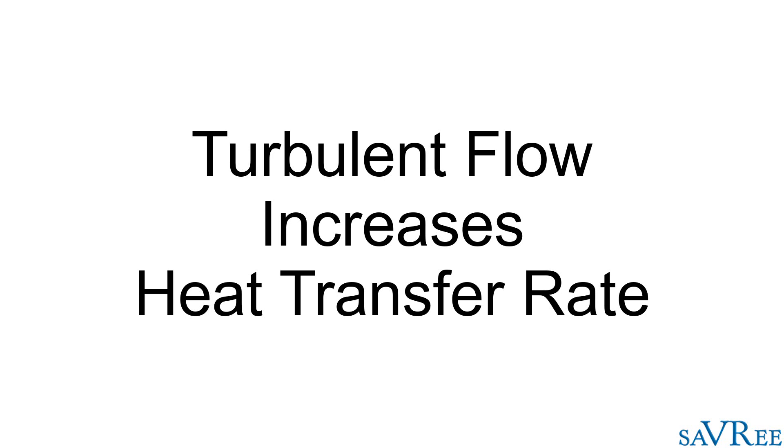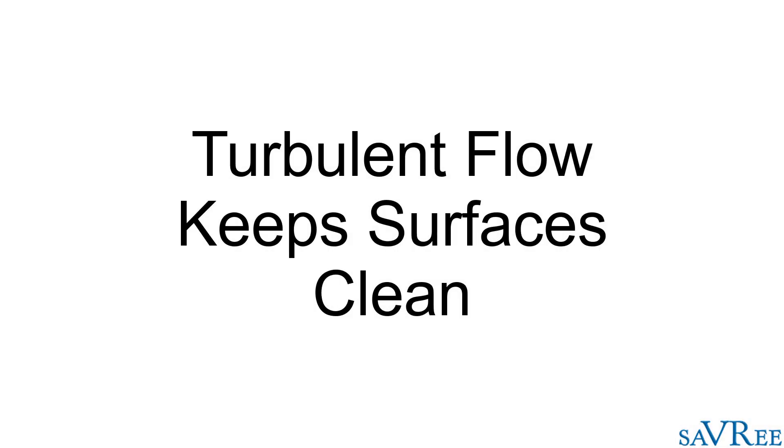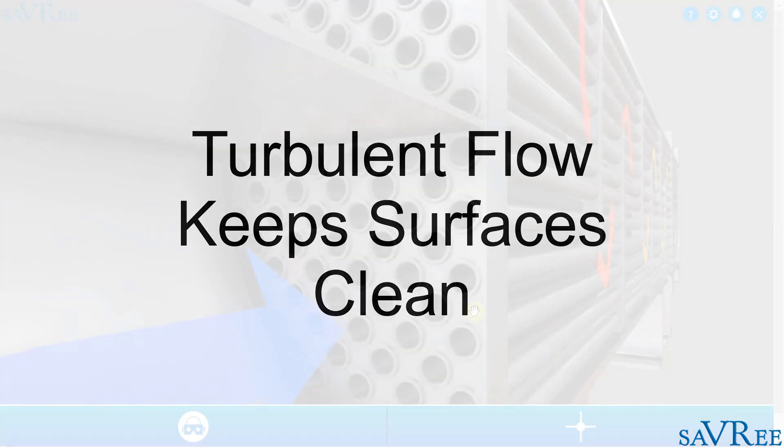The other benefit with turbulent flow is simply that if we have suspended bodies within the fluid that may stick to the sides of the tubes, they won't be able to stick to the sides of the tubes as easily. If they do stick to the sides of the tubes, that is going to reduce our heat transfer rate or our heat transfer capacity. So by having this turbulent flow, we're preventing them or reducing the risk that they're going to be able to stick to the sides of the tubes and this will maintain our heat transfer capacity.